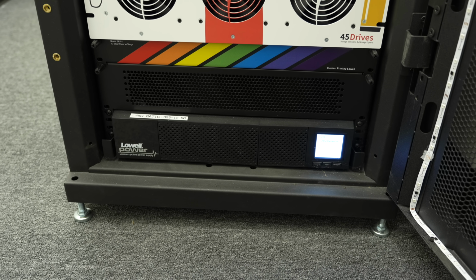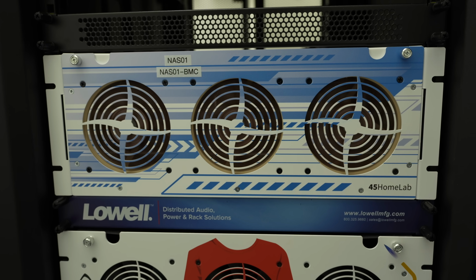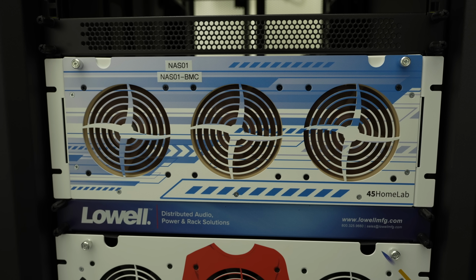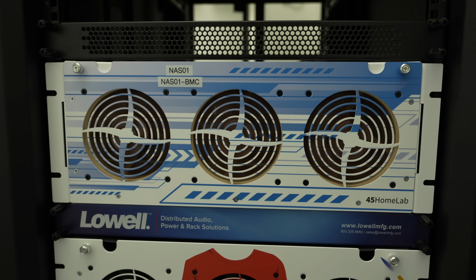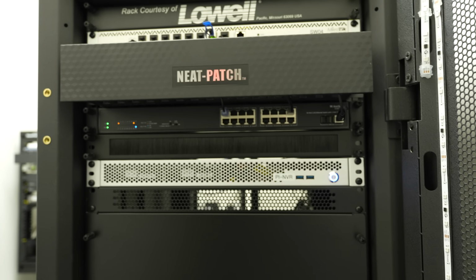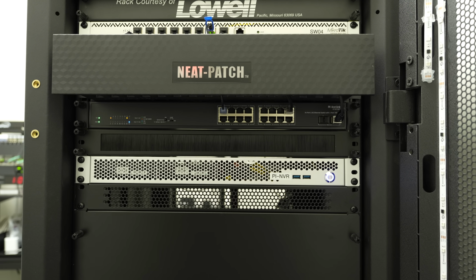I was actually kind of surprised, the load is only 11% here. It's not that much load, so I really got an hour of runtime. You'll see in a minute when the NAS shuts down, I actually got more runtime after it shut down, because the UPS sees even less load and thinks it can run longer. But the other equipment is still running at this point. We're only 10 minutes in.